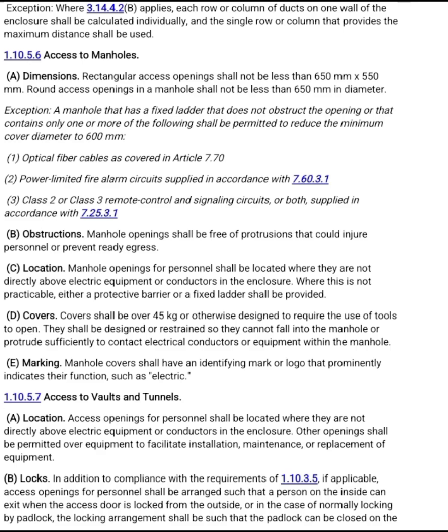B. Obstructions. Manhole openings shall be free of obstructions that can injure personnel or prevent ready egress. C. Location. Manhole openings for personnel shall be located where they are not directly above electrical equipment or conductors in the enclosures. Where this is not practicable, either a protective barrier or a fixed ladder shall be provided. D. Covers. Covers shall be over 45 kg or otherwise designed to require the use of tools to open. They shall be designed or restrained so they cannot fall into the manhole or protrude sufficiently to contact electrical conductors or equipment within the manhole. E. Marking. Manhole covers shall have an identifying mark or logo that prominently indicates their function, such as electric.